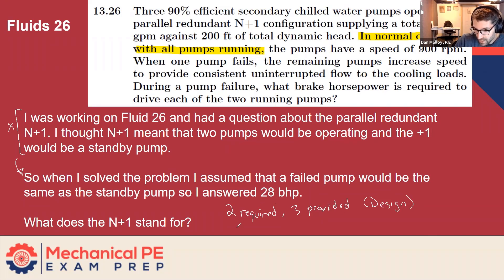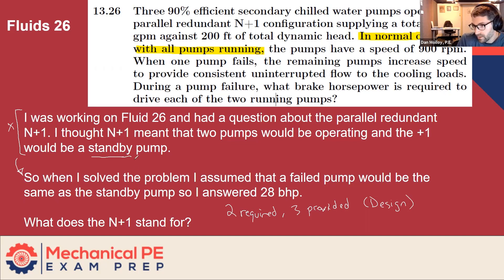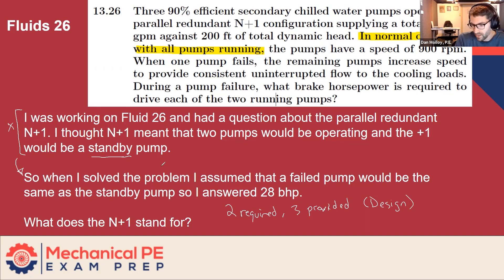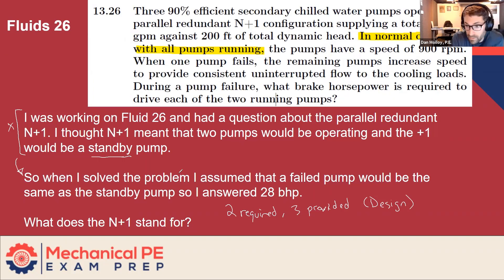Some operations may say exactly how you interpreted this — two running and one standby. And that's totally viable, nothing wrong with that. One of the concerns that comes up is maybe when one of them fails, the third one won't start up for whatever reason, so now you've got a controls dependency. There's also a bit of a gap in delivery — the water will briefly stagnate in the system and then get going again when the standby pump starts up. Maybe that's not a big deal, maybe it is — depends on what you're dealing with.